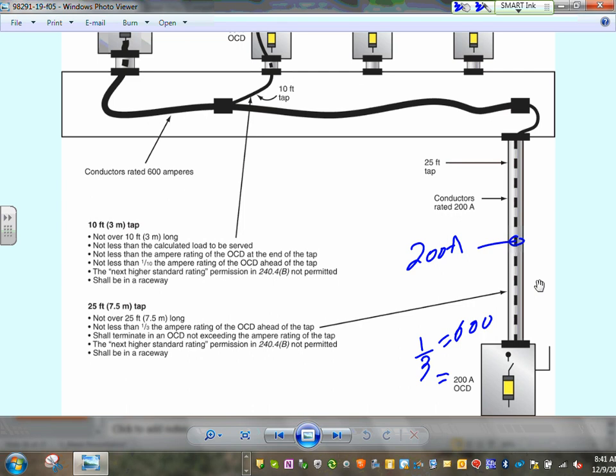That would be 3/0. What did we size it? That would be 4/0 AWG. Then you have to fuse it with the same amount of current, guys. Here's 200, you put a 200 amp here. You have to fuse it. You have to put it in a conduit, rigid metal conduit or EMT. It cannot be longer than 25 feet. So that's basically the rules for the 10-foot or 25 feet.